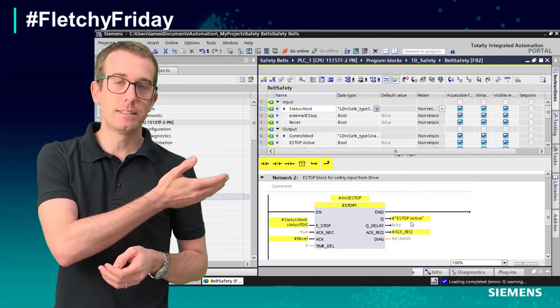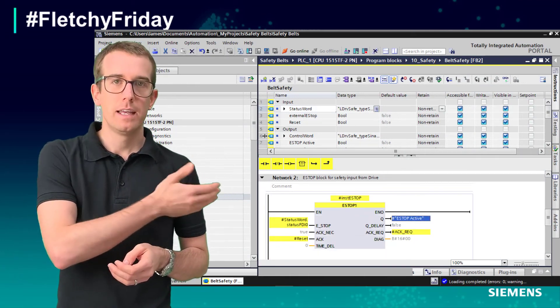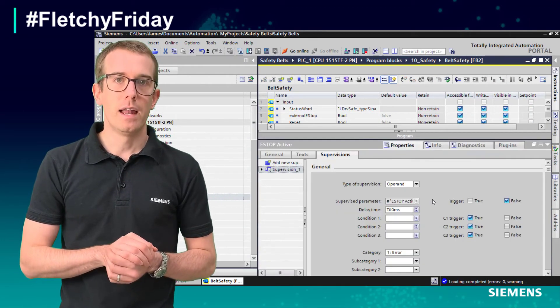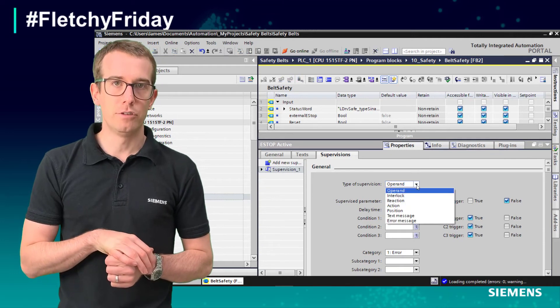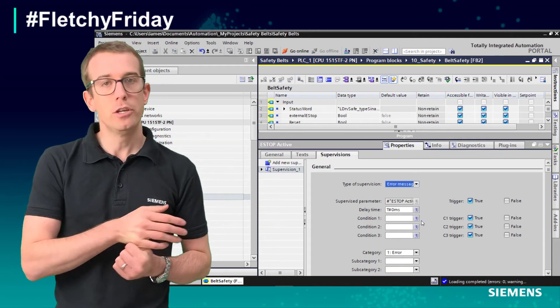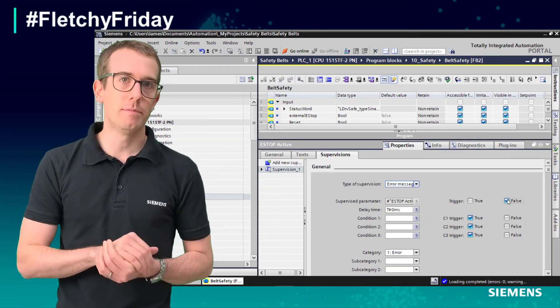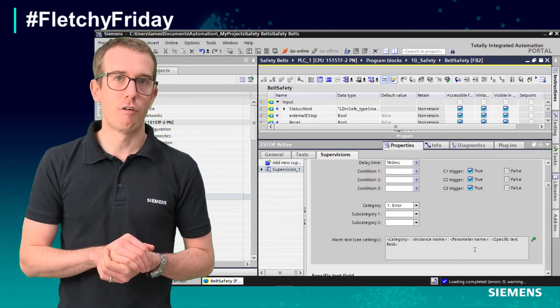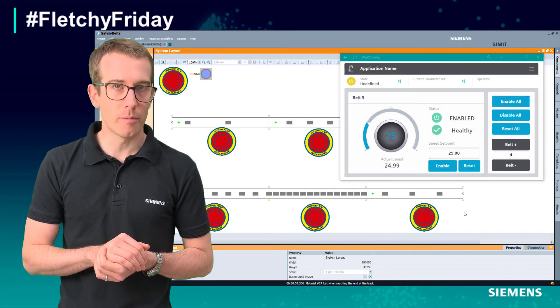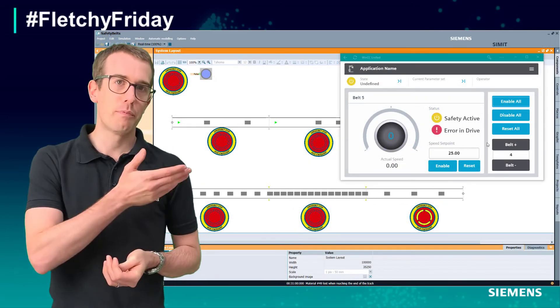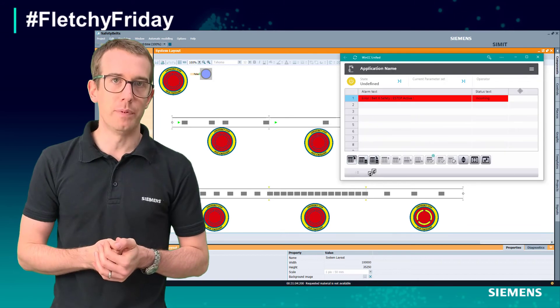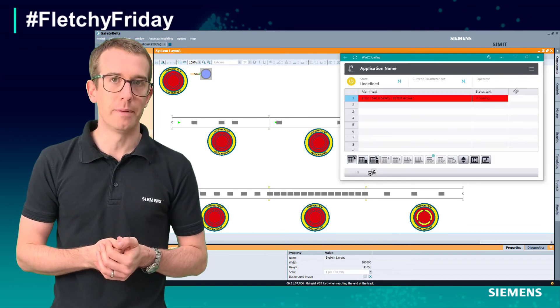Here is my safety code, here is the bit for my e-stop, and I simply add a supervision. You can see the alarm text will be automatically generated from my symbolics and tag comments. During operation, we press the e-stop and the alarm message appears on the HMI.